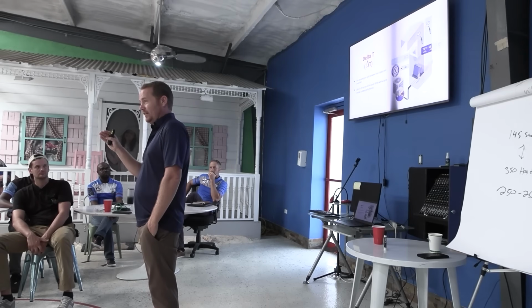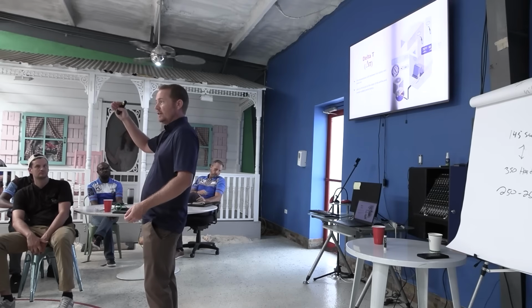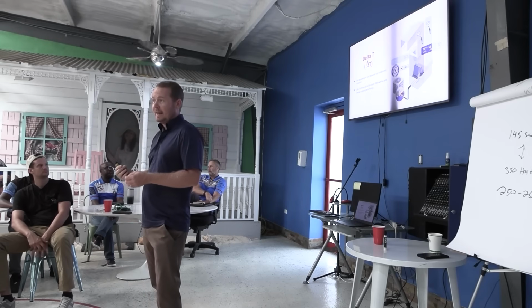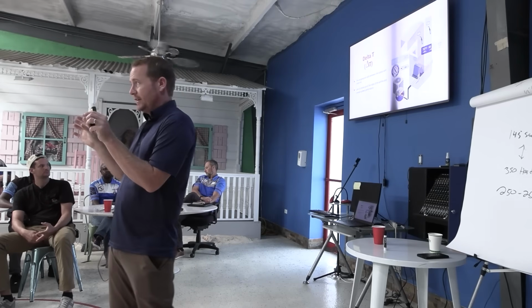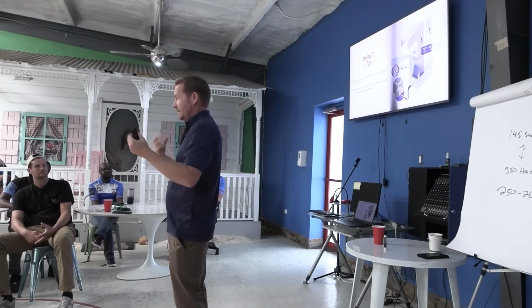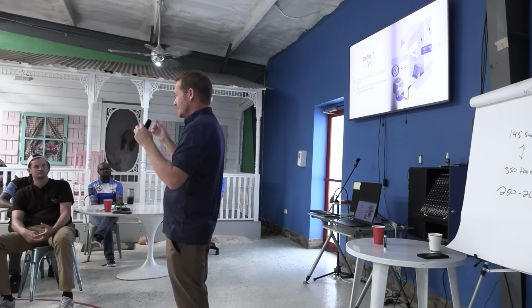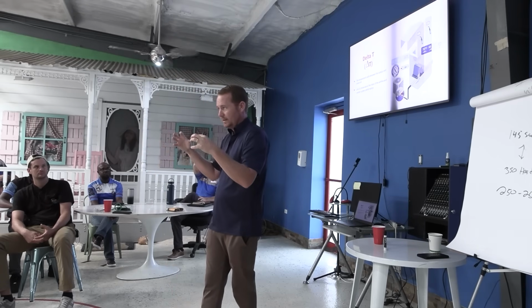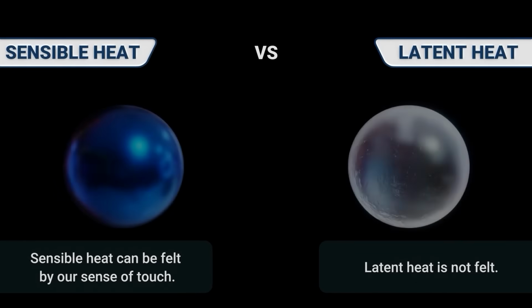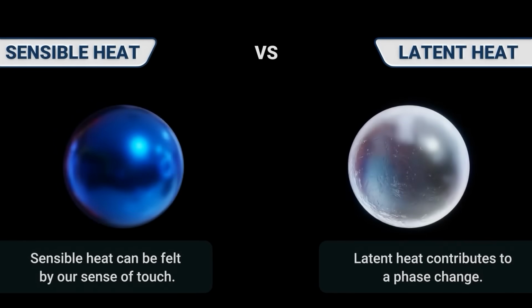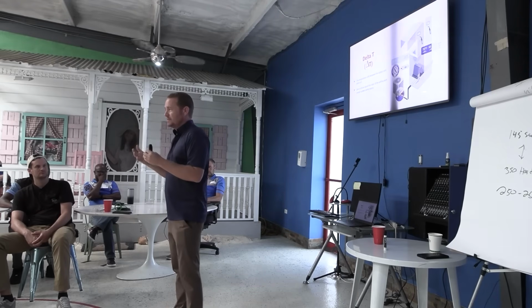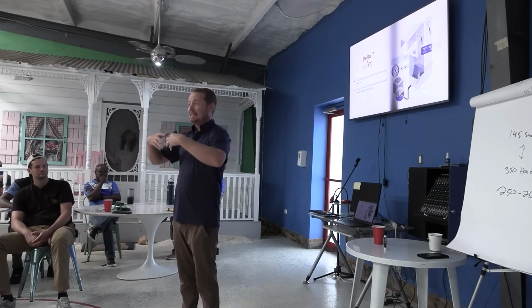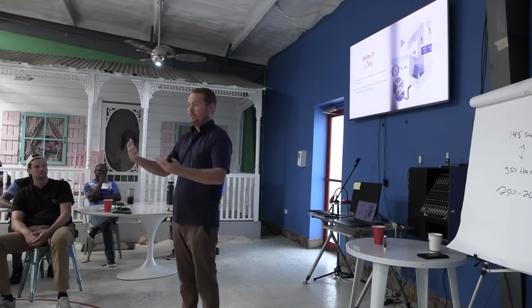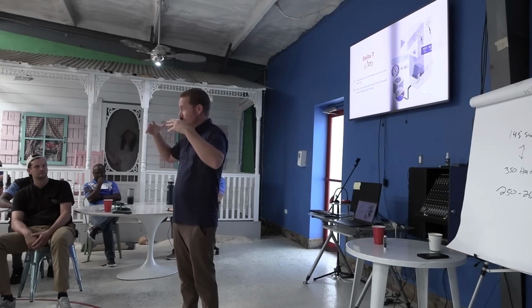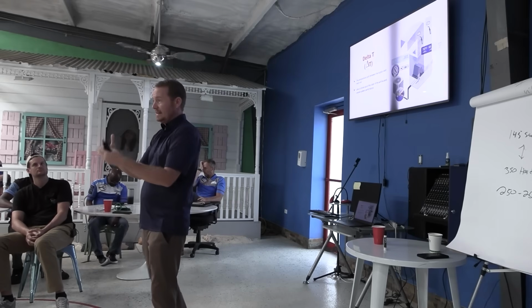Now it shouldn't stay that way though. As the house dries out, that delta T should start increasing on you. And the reason for that, if this is hard to understand, just remember it's this sensible latent thing. We're not going to go too deep with this group, that's a little basic, but I'll cover it quickly. Sensible means heat that goes towards changing temperature. Latent means heat that goes towards changing things from liquid to vapor, or vapor to liquid. There's two different types of latent: there's the latent that happens inside your coils, inside your condenser and your evaporator, that goes to the boiling of the refrigerant or the condensing of the refrigerant.